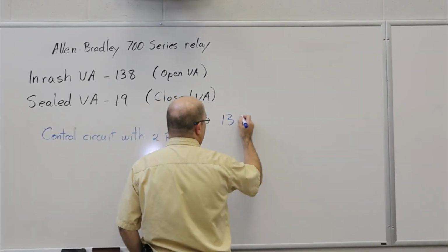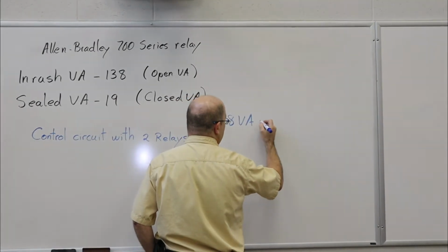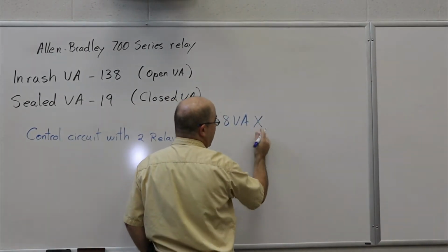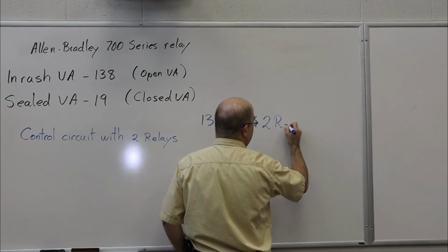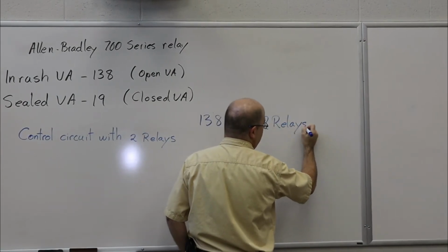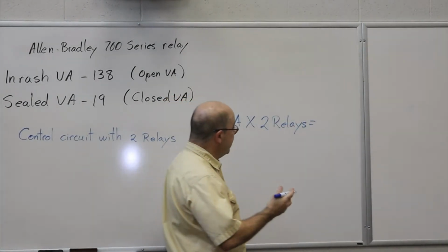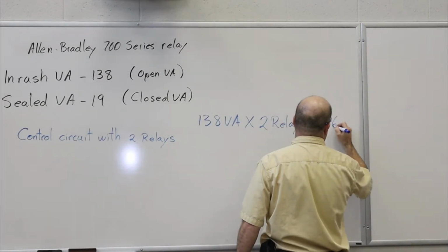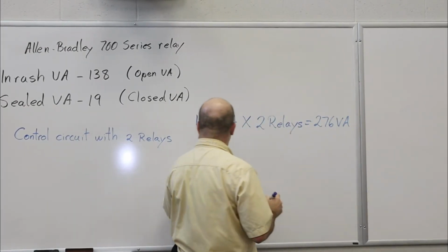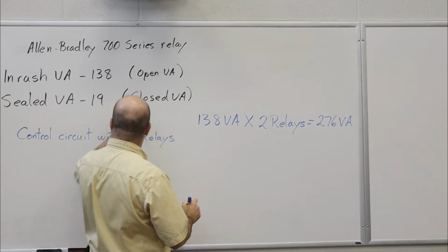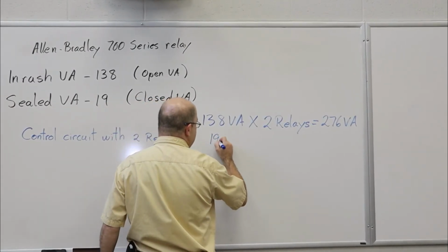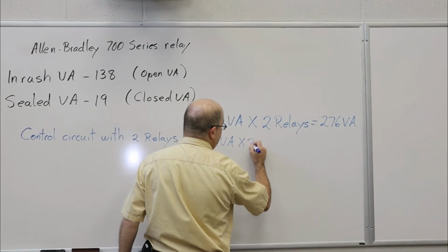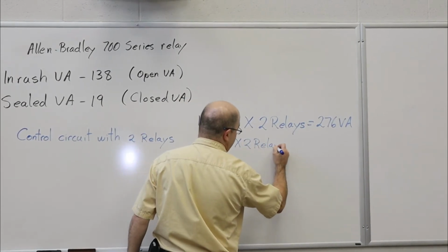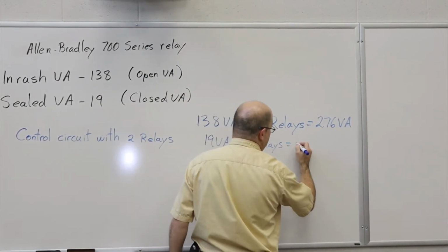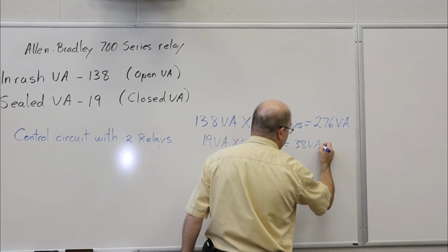In this case, 138 VA, which is an open value, we're going to multiply that by two relays. And as a result, I'm going to need 276 VA. And now for holding, or the sealed VA, we're going to take the 19, multiply it by the two relays, and that's going to be 38 VA.